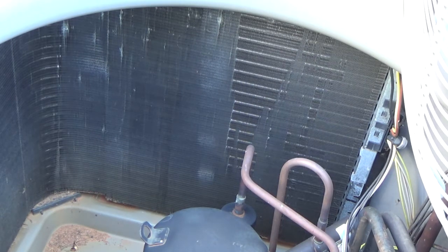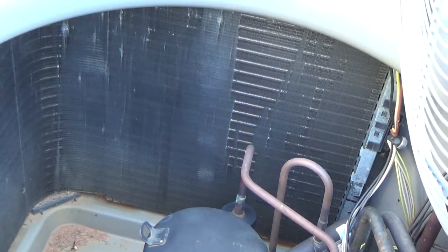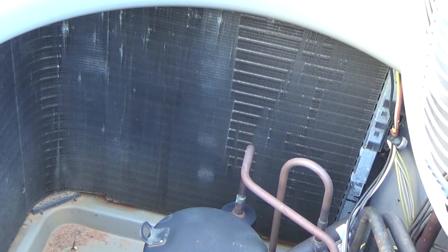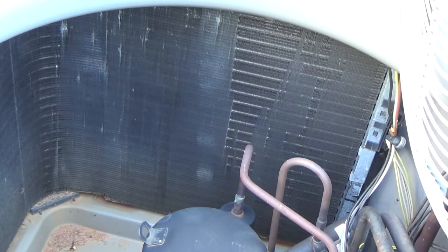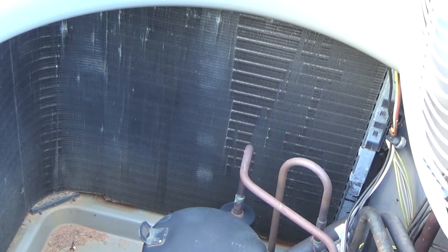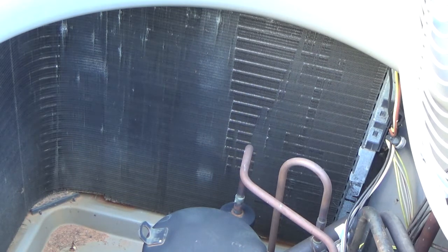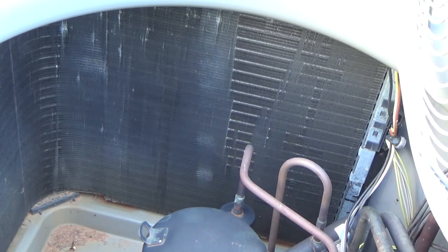Also, you might have seen these hose things you can put on your coils, supposedly cooling it down because water sprays on the coils. Well, that's for people who don't really understand physics or thermodynamics. No matter how hot it gets - 110, 115, 120 degrees - it's the temperature difference that matters. If you're in air conditioning mode and it's 110 outside, these coils are going to be hotter than 110, so there's a delta between the ambient temperature and the coil temperature, and that difference is what transfers the heat.